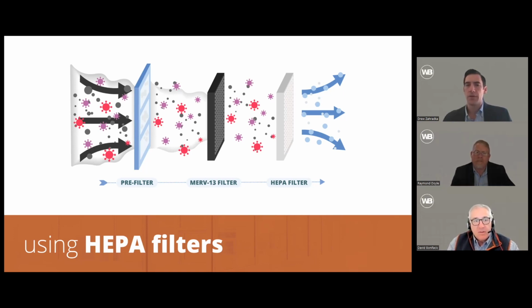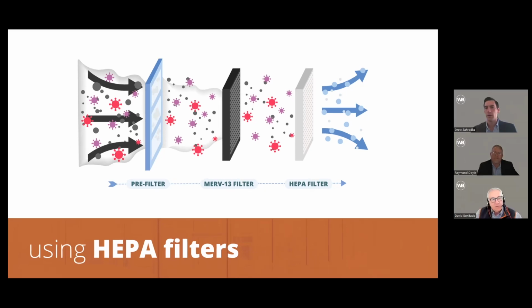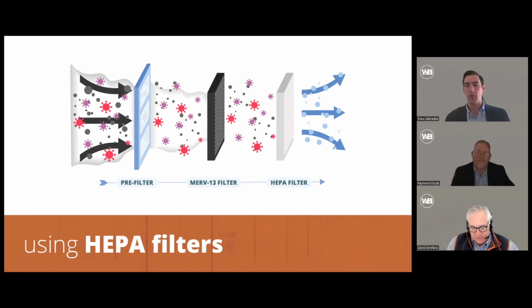So that's something you need to establish with the end user at the beginning of the project, understanding what the science within the space is. And again, if there are any risks with contaminants due to the science in the space, the end users typically give that requirement based on the chemicals they may be using, or the exposure that's there. Whether it's allowed to be recirculated within itself, it can be recirculated and shared with adjacent spaces, or if it needs to be once through air, where air comes in and then it's exhausted out of the building.